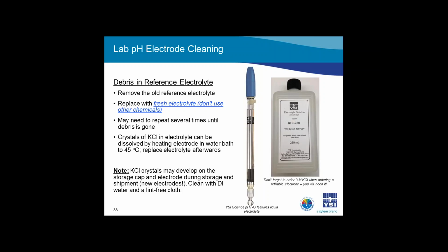It is very normal for KCl crystals to develop on the storage cap, electrode, and around the filling hole during storage. New electrodes may also have salt crystals. This is normal, and they can be cleaned off by rinsing with DI water and wiping with a lint-free cloth.